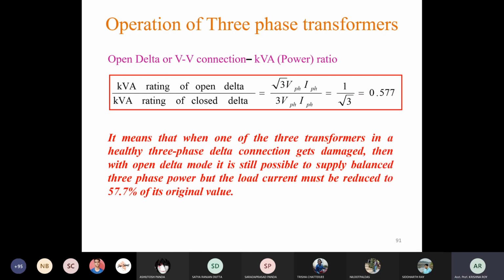So it means that when one of the three transformers in a healthy three-phase delta connection gets damaged, then with open delta mode, it is still possible to supply balanced three-phase power, but the load current must be reduced to 57.7% of its original value. Then only we will be able to supply the existing load. That is why it was claimed at the very beginning that we can supply three-phase loads with this open delta connected system, but at a reduced level.